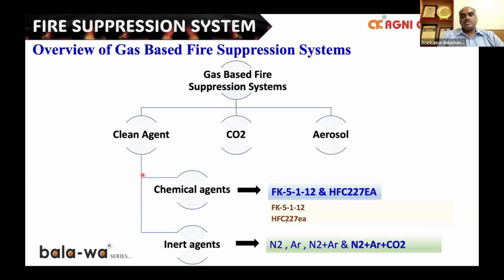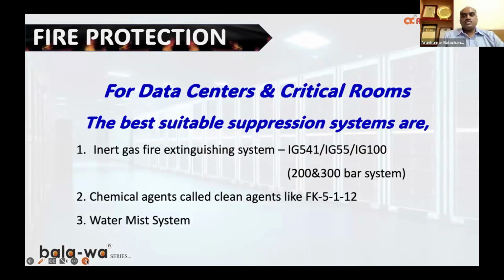Clean agent is in turn classified into chemical agents, that is chemical based fire agents like the FK-5-1-12 and HFC 227, and inert based agents like nitrogen, argon, or the combination of nitrogen, argon, and CO2. For data centers and most critical rooms, the best suitable suppression systems are the inert, which is 100% nitrogen, the IG100 system, or 50% nitrogen and 50% argon, which is the IG55 system, or a combination of 50% nitrogen, 42% argon and 8% carbon dioxide, which is the IG541 system.